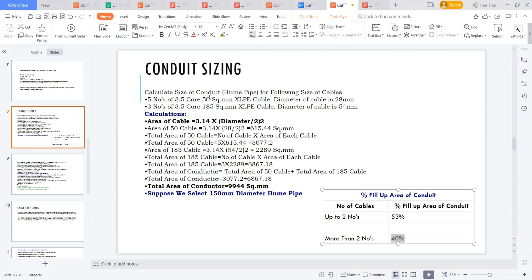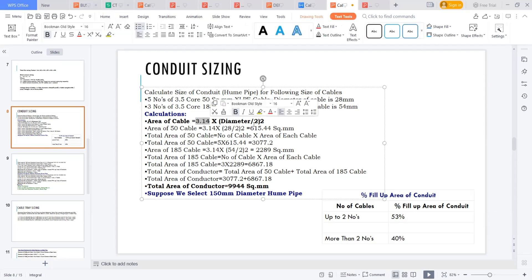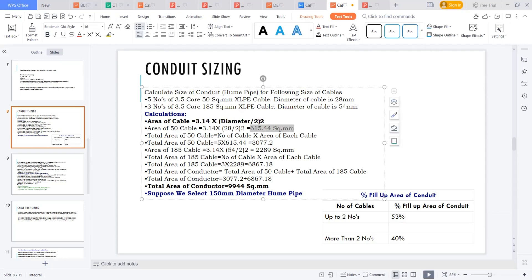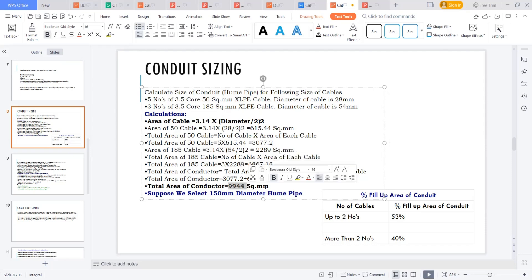The cable area is calculated as π r² = π × (d/2)². The 50 sq mm cable has an area of 615 sq mm; multiplied by five cables gives approximately 3,075 sq mm. Similarly calculating for the 185 sq mm cable and adding all values, the total area of all conductors required is approximately 9,940 sq mm.